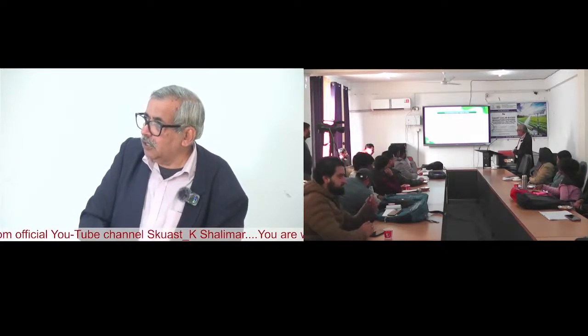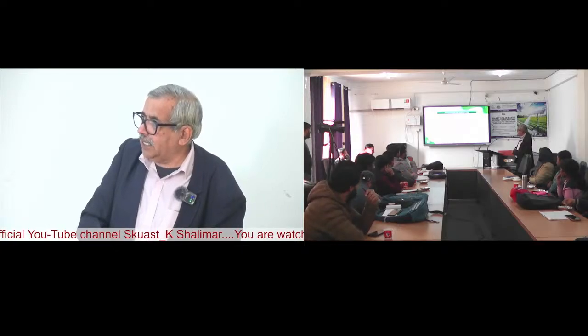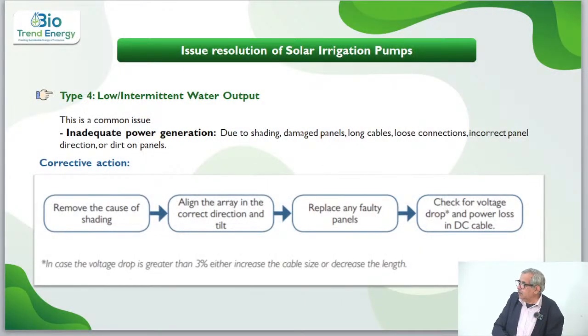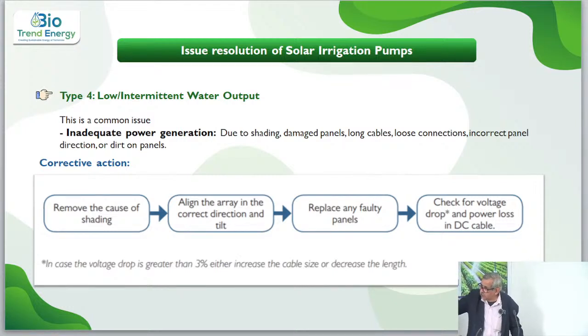so that needs proper cleaning. Remove the cause of shading, align the array in the correct direction and tilt, replace any faulty panels, and check for voltage drop and power loss in the DC cable. In case the voltage drop is greater than 3%, either increase the cable size or decrease the length, so the resistance becomes low in my connection. So these are some of, I would say, good engineering standard operating practices for a solar plant to get operated.